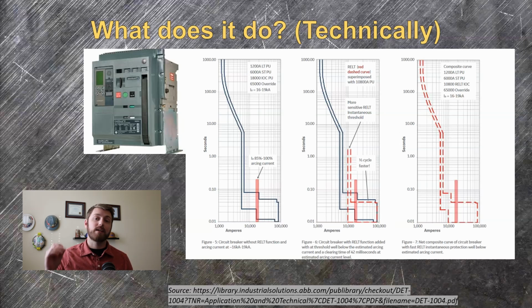It takes 18,000 amps to get that breaker to instantly trip. When enabled, with maintenance mode turned on, it doesn't affect the long time or short time pickup or the delay, but it will trip instantaneously at 9 times the continuous rating, 10,800 amps. This setting can be even lower if need be. In some cases, like with GE's RELT system for the IntelliGuard trip units, the breaker's instantaneous clearing time is further reduced by some sort of proprietary black magic. It actually makes the breaker trip faster.